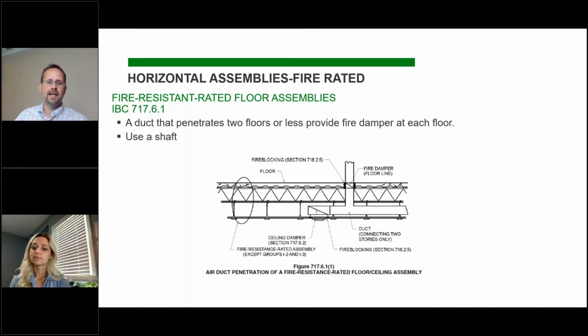So the code says that if a duct penetrates 2 floors or less with fire rated floors, you don't have to have a shaft if you have a fire damper at each floor. Obviously, you can always add a shaft, and that meets code if you don't want to have fire dampers, because to be honest with you, fire dampers in a floor are very difficult to access depending on where they're at, and pretty difficult to install just because of the clearances during construction. The clearances in that concrete, depending on the floor type, can be difficult to get that damper in and get it installed, and the coordination.